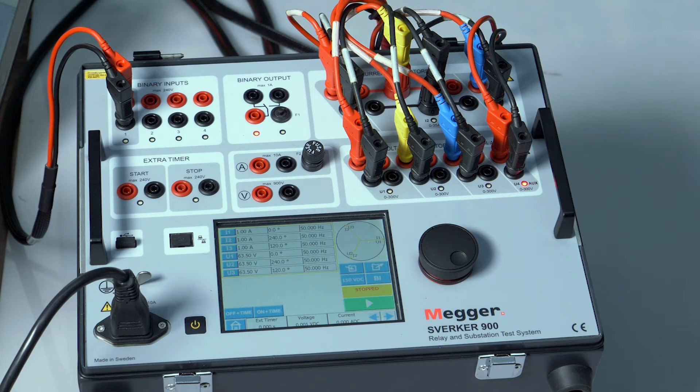Multiple harmonic injection. In many applications, multiple harmonics such as second harmonic for transformers, third harmonic for generators may be required to be injected for testing of relays. In Sverker 900 we can inject multiple harmonics.